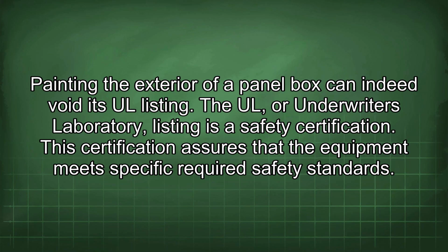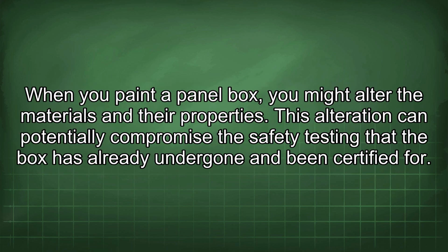Painting the exterior of a panel box can indeed void its UL listing. The UL, or Underwriter's Laboratory listing, is a safety certification. This certification assures that the equipment meets specific required safety standards. When you paint a panel box, you might alter the materials and their properties. This alteration can potentially compromise the safety testing that the box has already undergone and been certified for.